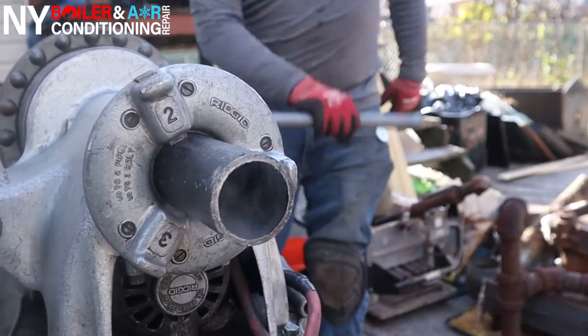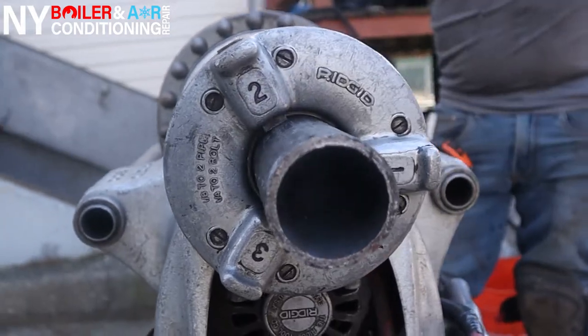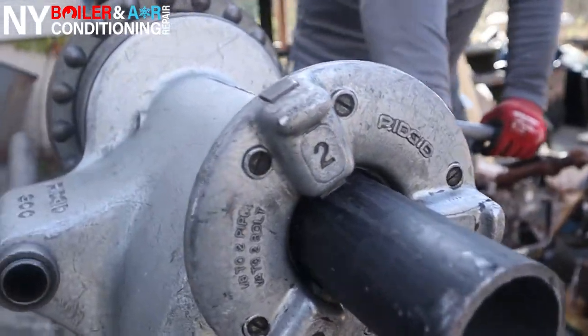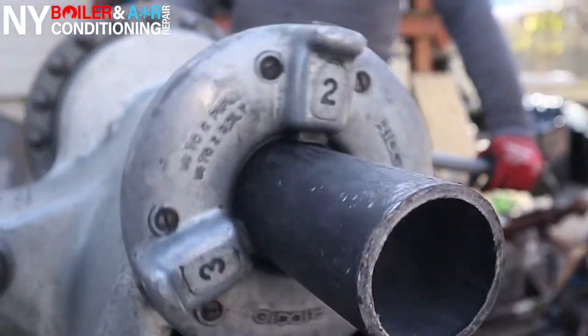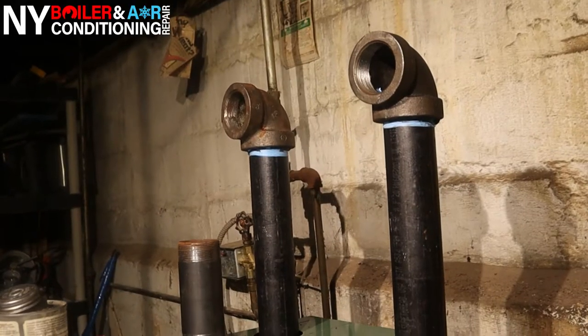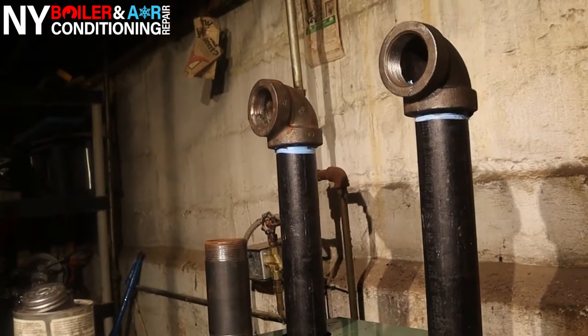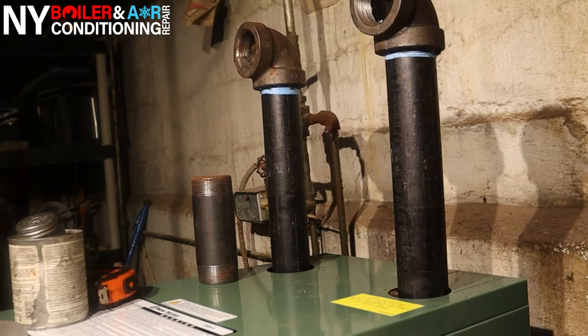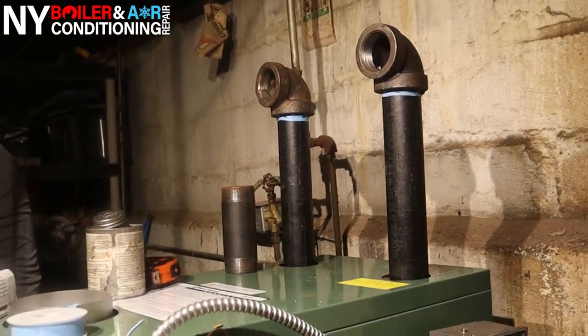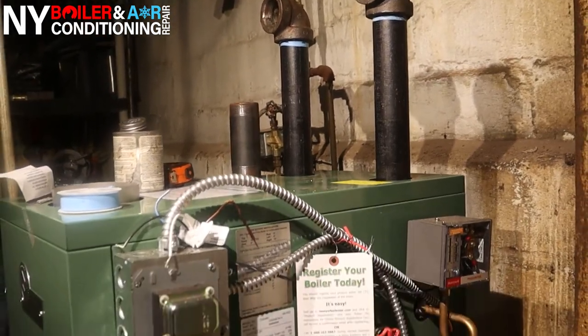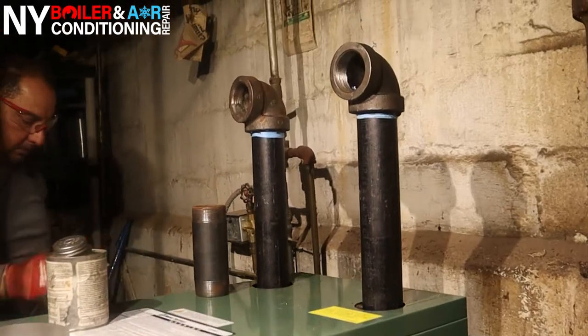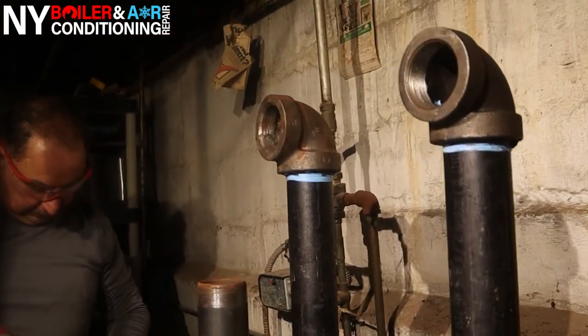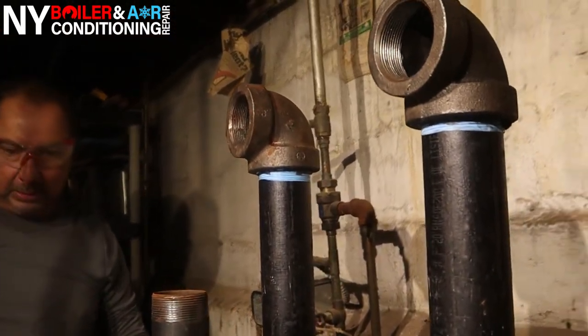As per the instructions, we need to get a riser, both risers - we're going to use both of them in this case and manifold them together. You see the nipple right now on the left hand side, one on the left, one on the right. We're going to take those out and use one nipple with an 18 inch nipple, another 18 inch nipple on top of the boiler. Once we put the two 18-inch nipples in, we're going to put in two elbows, face them towards the exhaust piping, and manifold them together.